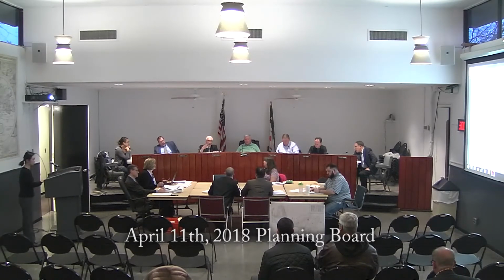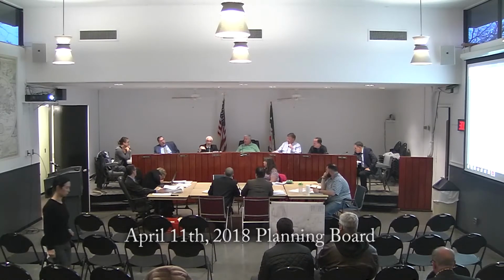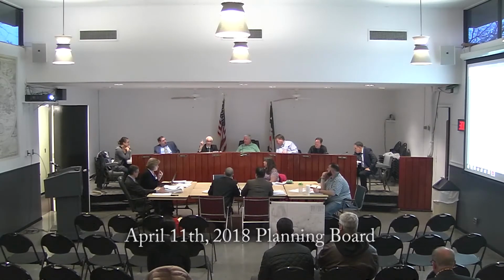Let's back up, because this is something I know about. The cooling towers, unless the AC equipment is starting up at night - if your AC is cooling the system 24/7, the cooling towers are running 24/7. So don't tell me the cooling towers are suddenly starting at midnight. They're certainly not testing the generators at night. Something's happening at midnight, so it might be in your best interest to figure it out and let the buildings department know what's happening.